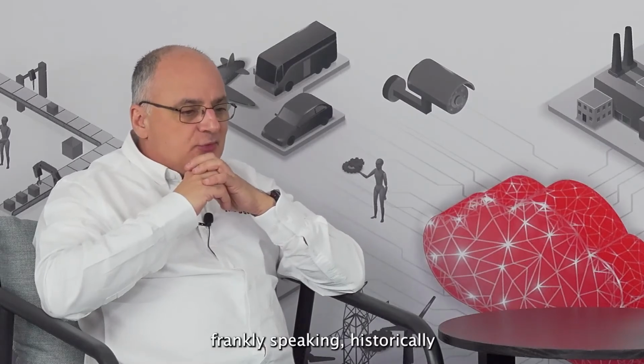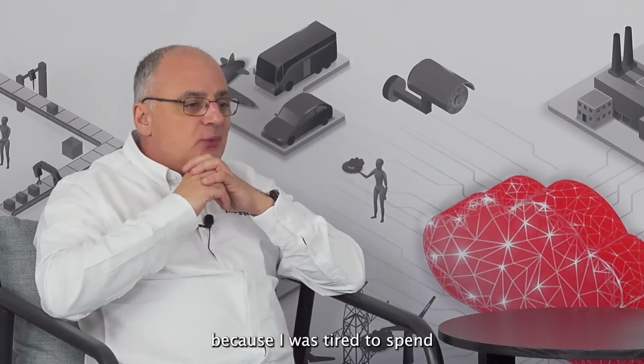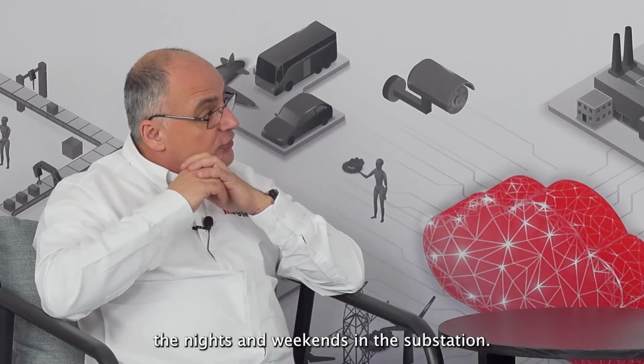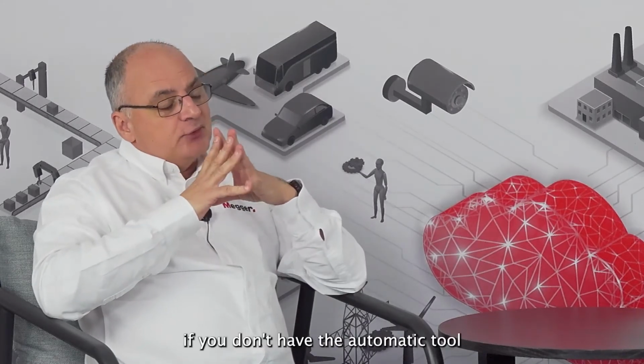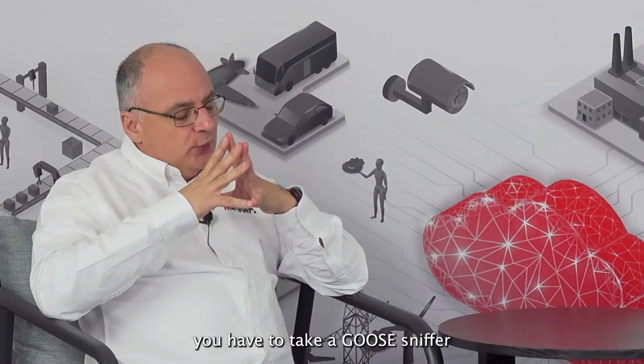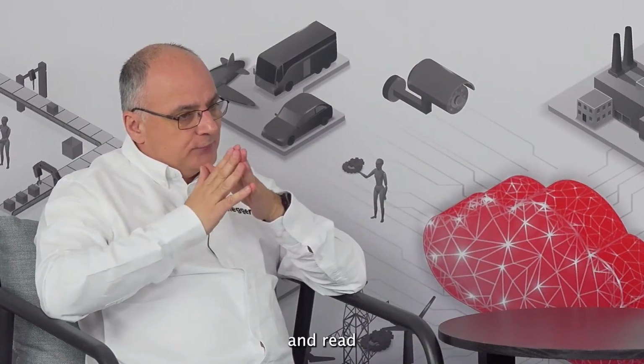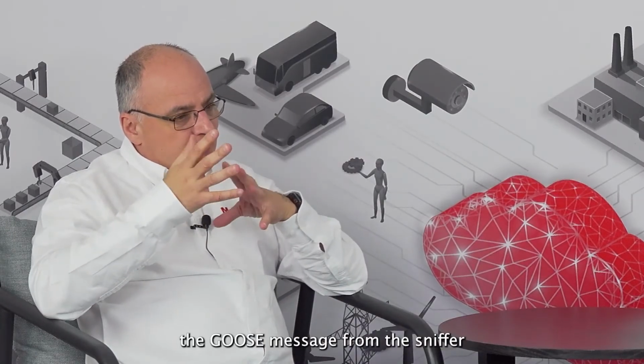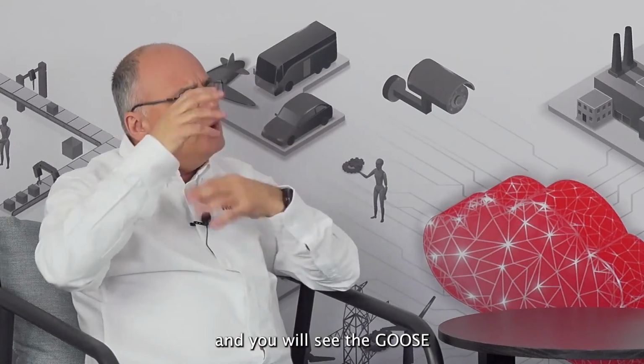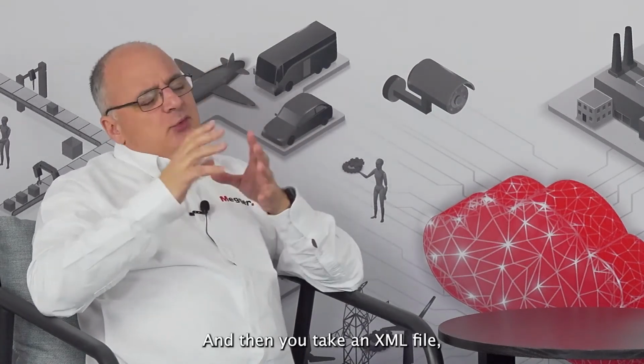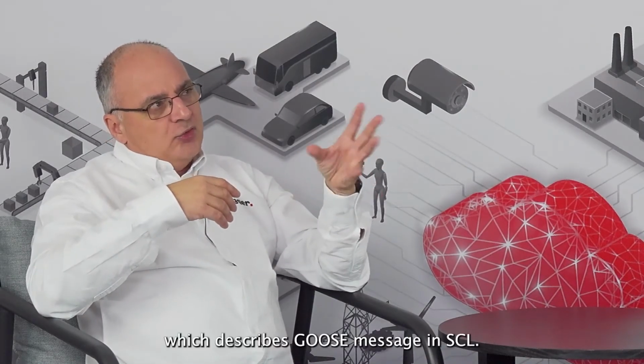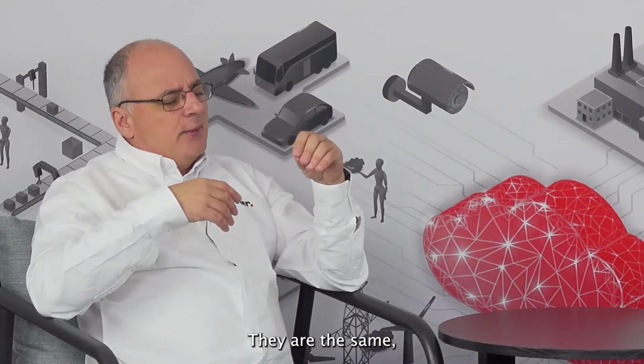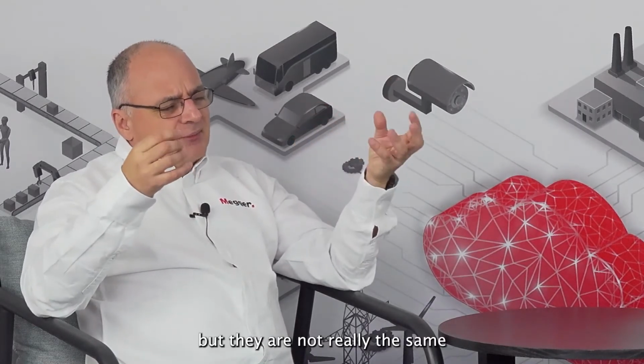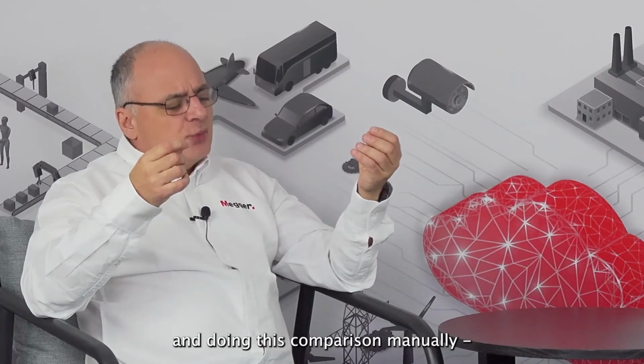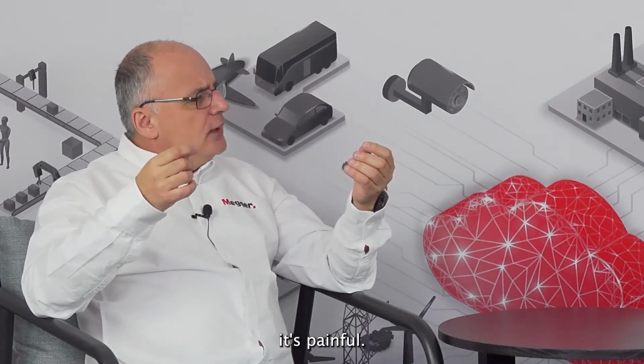Okay, frankly speaking, historically, the idea to do this was my idea, because I was tired of spending nights and weekends in the substation. Because if you don't have the automatic tool that does this for you, you have to take a GOOSE sniffer and read the GOOSE message from the sniffer. And you will see the GOOSE in a certain way. And then you take an XML file, which is the SCL file, which describes the GOOSE message in SCL. They are the same, but they are not really the same. And doing this comparison manually, it's painful.